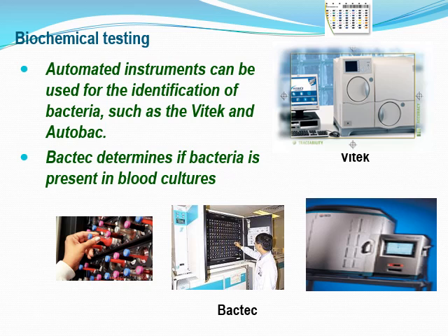The automated instruments, like the Vitek and the BACTEC, not only identify the bacteria, but they can also determine if bacteria are present in blood cultures. If you see that picture all the way to your far left, it's very sensitive and takes out a lot of human error. Of course, with anything, there are issues with the instrumentation as well, but if you are doing all your maintenance checks, keeping up with your calibrations, and running your quality control, these are very good in big, large hospitals.